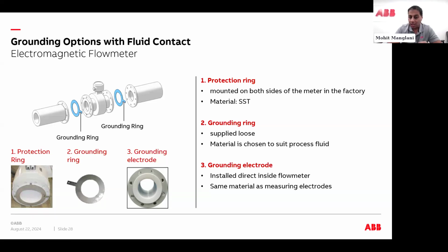The other way to accommodate grounding is using a grounding electrode. As I mentioned, a mag meter has 2 electrodes, typically at 3 o'clock and 9 o'clock. That's absorbing that voltage, right, to give you that flow reading. There's another electrode that we have that goes at the 6 o'clock that'll connect it directly to a ground. The grounding electrode, it's not that great, because if you have an application which has a little bit of solids in it, over time, solids will settle on the bottom of the meter at 6 o'clock. So it'll eventually coat the electrode, the grounding electrode.